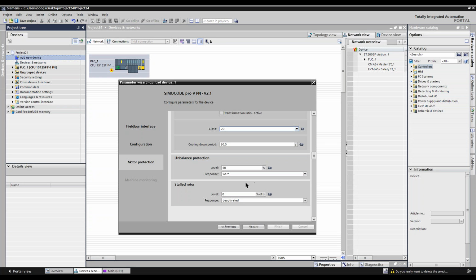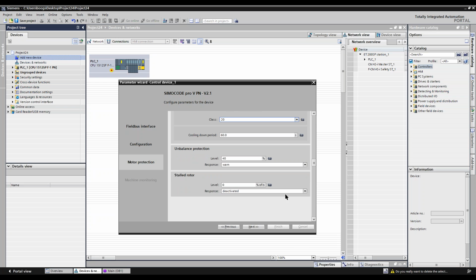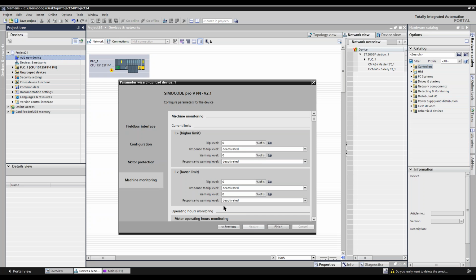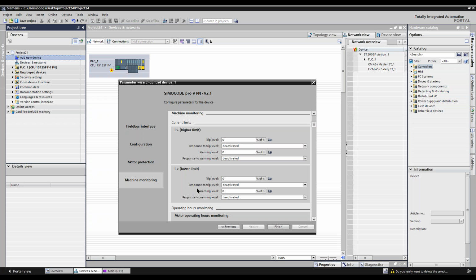Okay, unbalanced protection. So phase loss, phase imbalance, and so forth. Stalled rotor. Now notice everything's deactivated, okay? It is deactivated, but it's an option waiting for you that you can use. All right, I'm going to hit next. Now here's some of that logic that we talked about earlier when we spoke about PLCs and having remote I/O. Here is some of the software logic. Let me emphasize this. On the software logic, let's say we have a pump and it has a certain amount of pressure, 50 psi, and it's running.